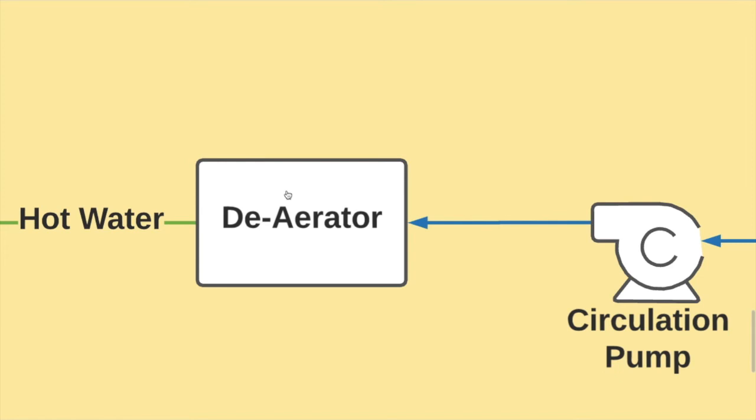The condenser and the turbine outlet operates under vacuum and all equipment leaks. So air will always leak into the equipment. The seams on the condenser are never perfect and the rotating shaft on the turbine is never perfectly sealed. Air always leaks in. And since oxygen causes corrosion problems in the steam system, we need to remove it. The deaerator heats the water and drives out all of the dissolved gases, including oxygen. This heats the water to 120 degrees Celsius. And that completes the cycle.